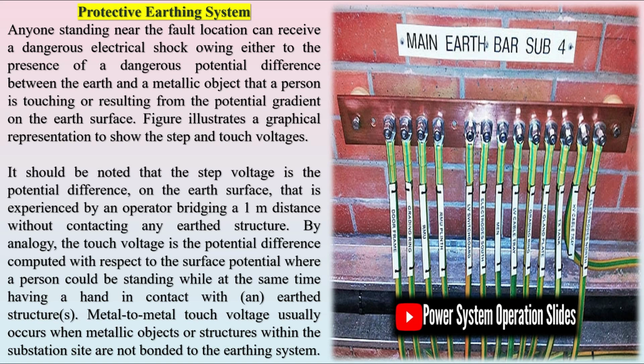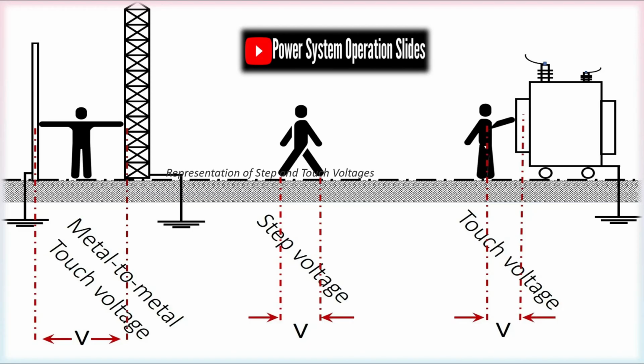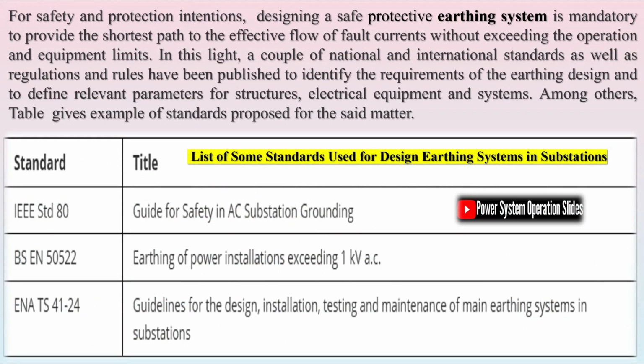Circuit breakers are usually used in large substations to interrupt any short circuits or overload currents that may occur on the network. Additional protection measures should also be considered, such as surge arrestors and fuses for protection of distribution circuits. The figure shows a simplified representation of an electrical substation. As can be seen in this figure, different protection measures should be considered in this system to protect both individuals and equipment. In general, high-voltage installations require an effective earth termination system in order to protect people against excessive step and touch voltages.